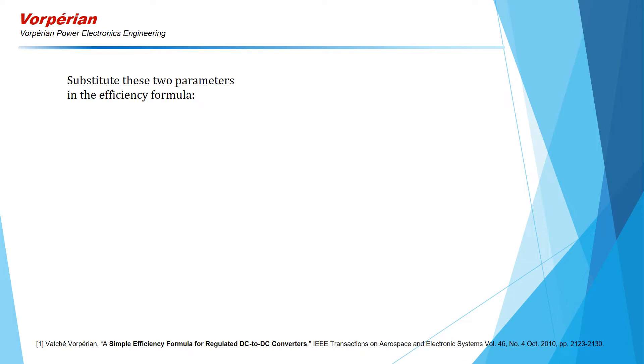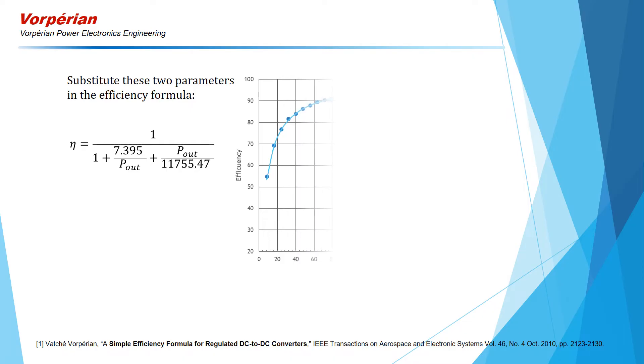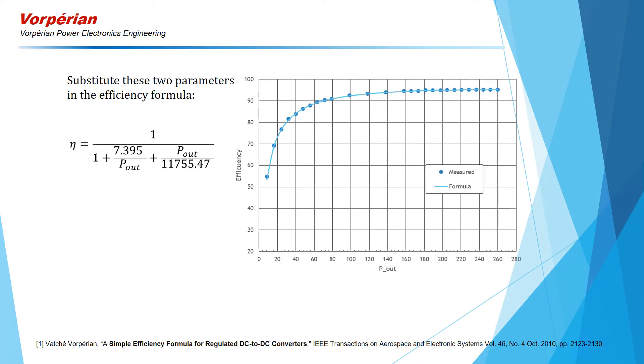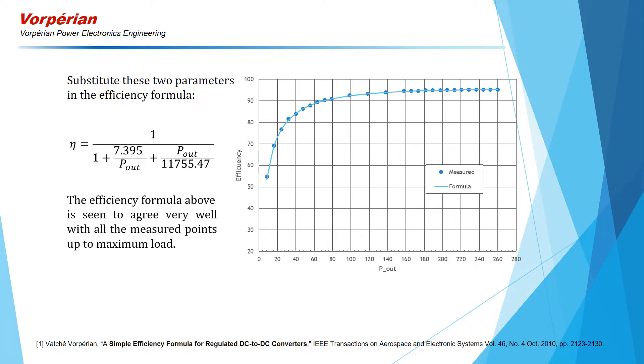We substitute these two parameters in the efficiency formula and we plot it. Here we see the solid curve given by the efficiency formula to be in excellent agreement with the measured values. The two parameters — 7.395 watts and 11,755.47 watts — were measured at two points: the no load point and the maximum load point.